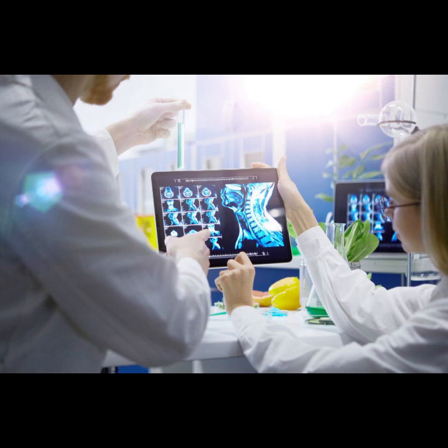Okay, that's neat. But how does that give us the whole picture? Well, here's the catch. That only gives us one level of phase information. To build up the whole image along the y direction, the machine has to repeat the entire process, excitation, phase encoding gradient, readout, many times. And each time, it applies a different strength or duration of the phase encoding gradient. So it steps through different amounts of phase shift.